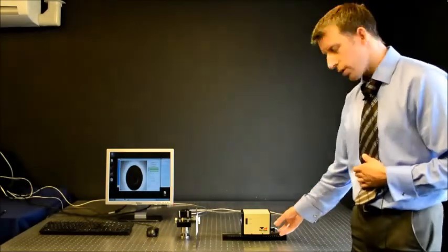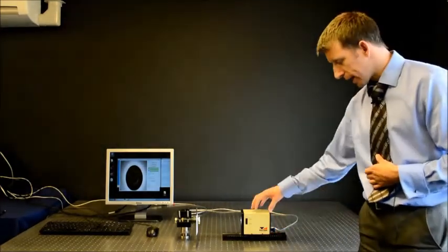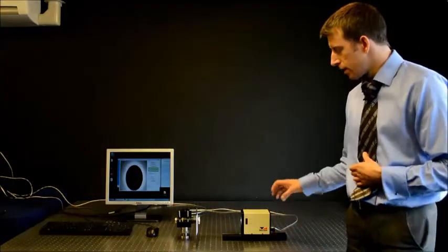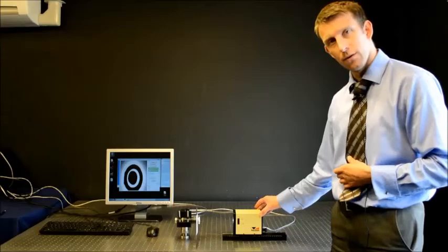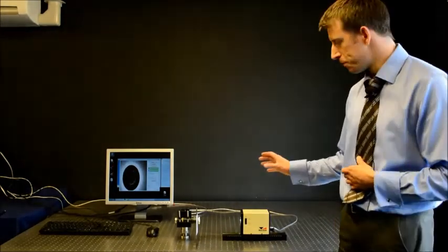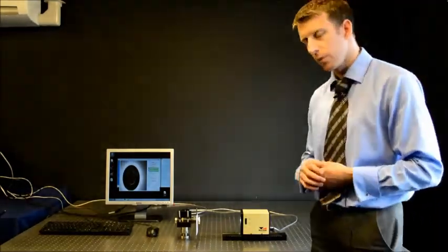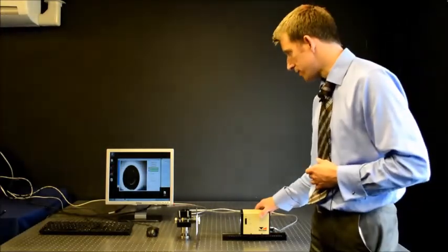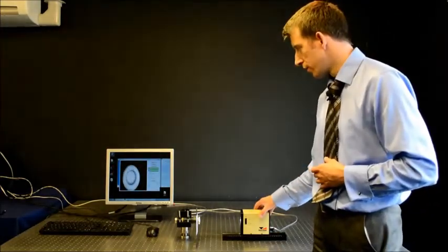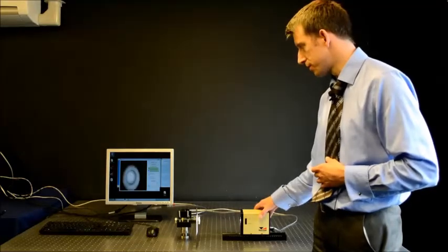We should no longer touch the second lens adjustment, but to get the source in focus, we should move the profiler on the optical rail. Firstly, we will increase the ND filter attenuation to get the camera out of saturation.